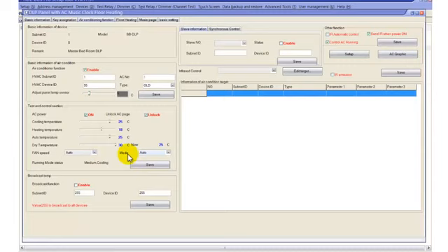We can test the module. We can also send commands. As you can see here, the running mode status now is medium cool. It's cool and the fan speed is medium. I can also keep it in cool and set the speed to high. When I save it now, it will change. Now it has changed to high cool. This is also for testing, so you can double check that you are connected to the right HVAC module. You can also see the actual temperature of the room, 25 degrees.